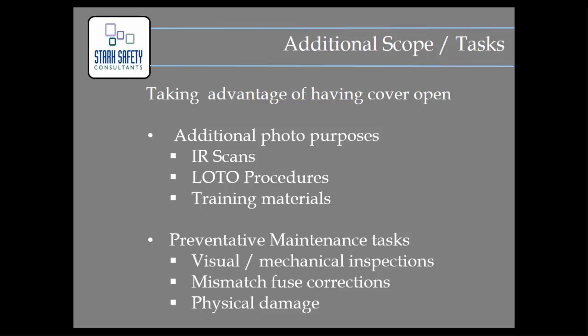Visual maintenance inspections. Again, if you can identify that you've done the visual inspection, and in the context of collecting the field data identify any piece of equipment that's of concern. A common one would be signs of water damage and rust that's actually rusted on the inside of the cabinet, excessive dust buildup, any signs of melted wiring and broken components, physical damage. Those are things that if you can put that in the RFP and define how you want them to report that, it's going to be a big value. From common practice, it's not something we're going to expect someone to go back and do at a later time because of the time involved in a big system. But if you can do it when that door's open, that would be a big value.